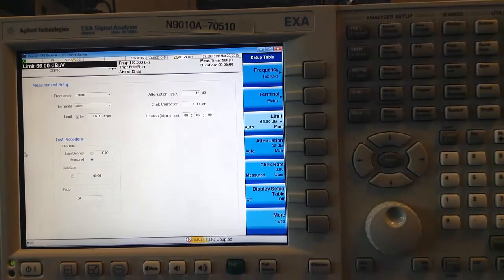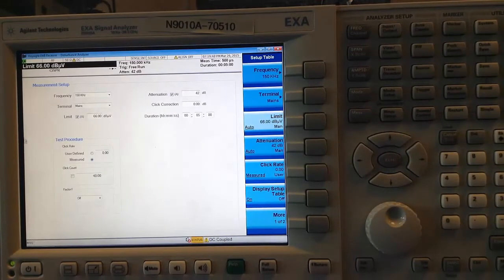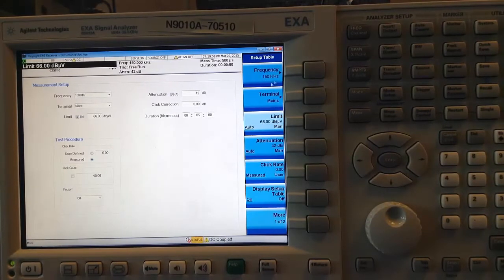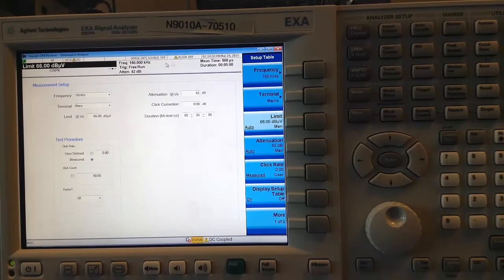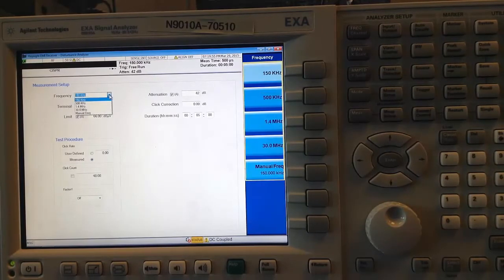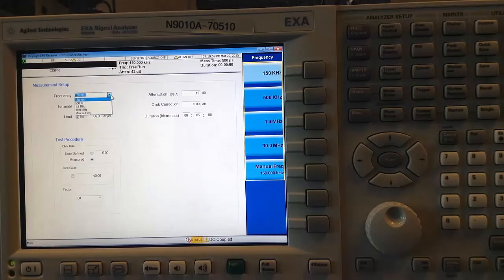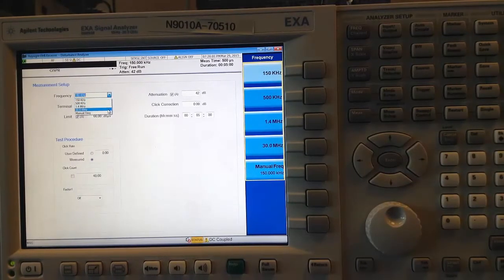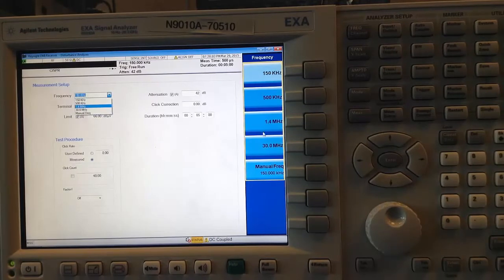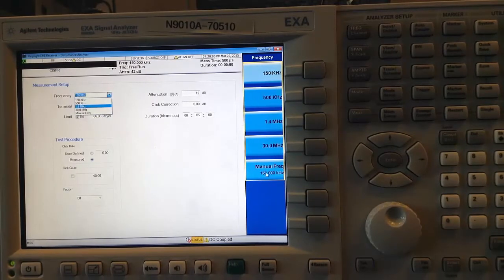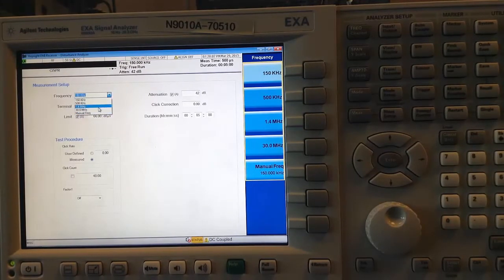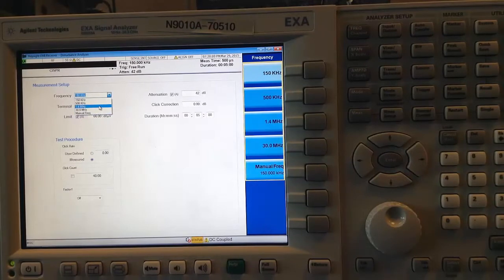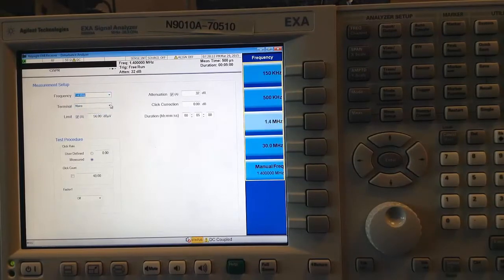The first thing to do is select the frequency. This can be done from this drop-down menu or from the soft keys on the side. CISPR 14-1 defines four frequencies where click measurements must be made. These are available directly in this drop-down menu as well as in the soft keys, but you can also manually select any other frequency of your choice. For now, I will select 1.4 MHz.